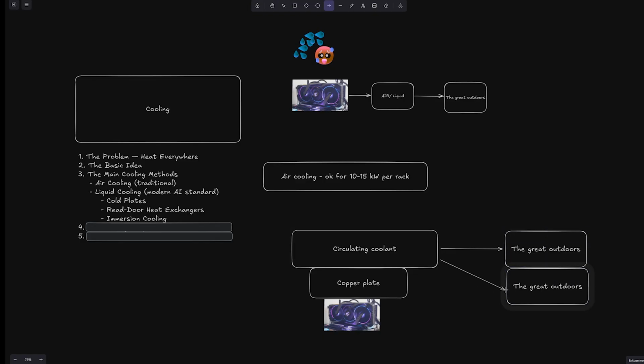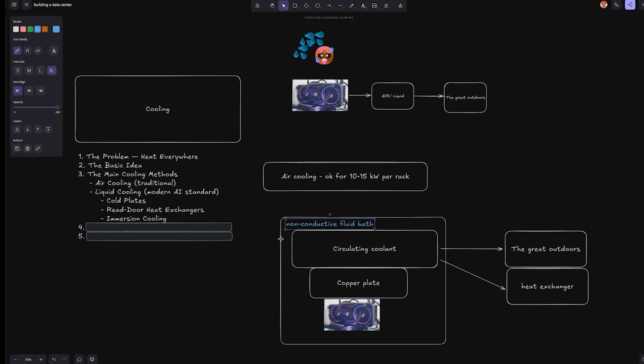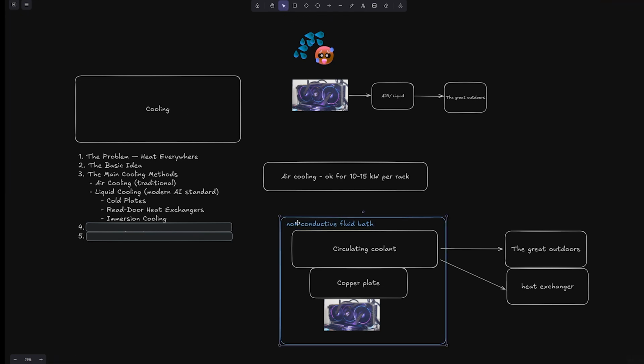There's another variation of these called rear door heat exchangers, where cold water runs through a radiator on the back of the rack and it captures the hot exhaust air before it enters the room. And the last option is called immersion cooling, which does, as it says on the tin, servers submerged in a non-conductive fluid bath. Fluid circulates through an external cooling loop. This solution is ultra efficient and silent and is used for very, very dense setups or remote setups.